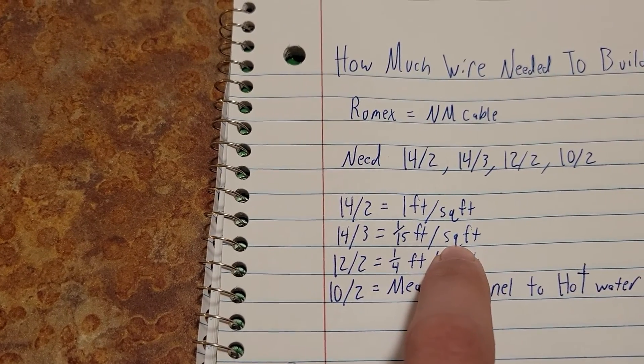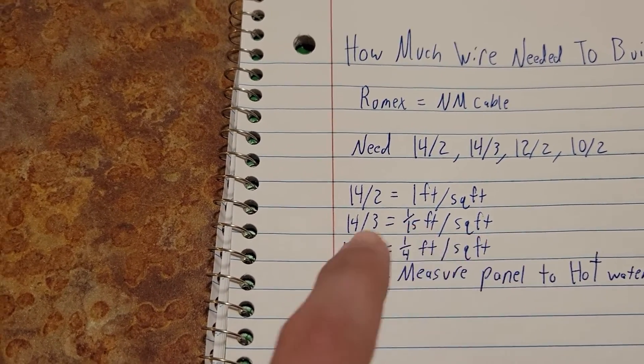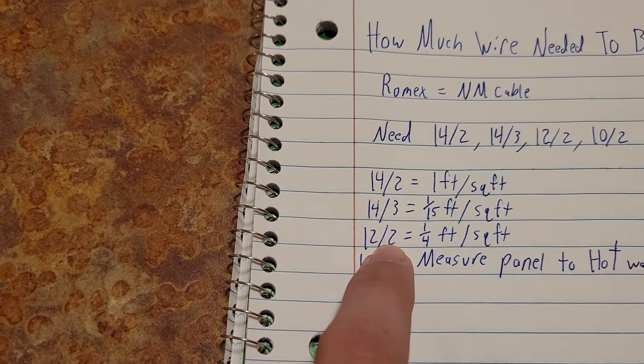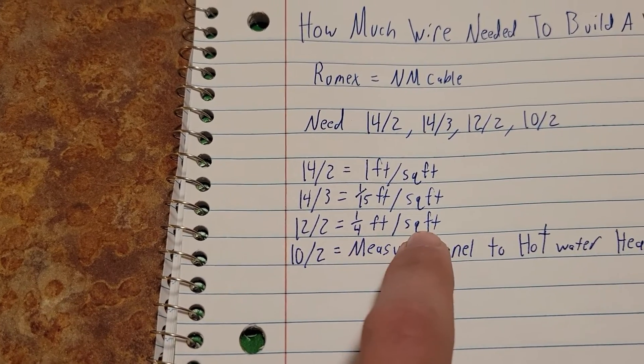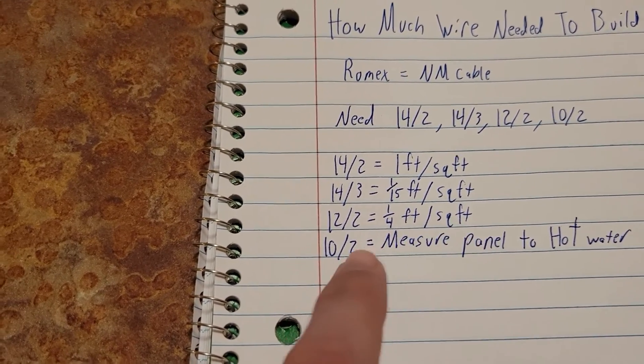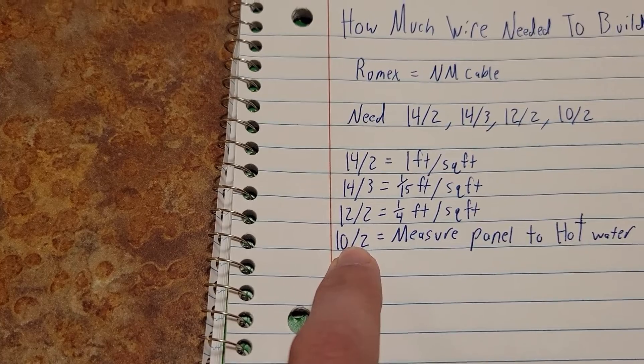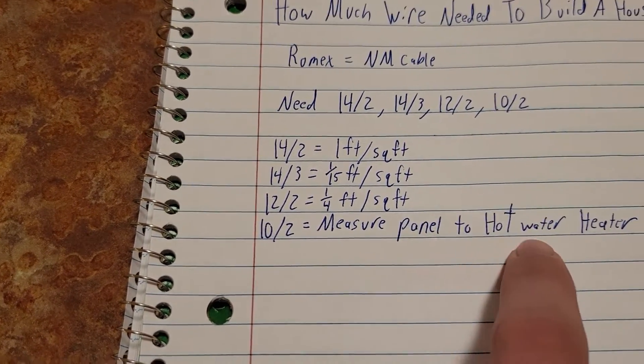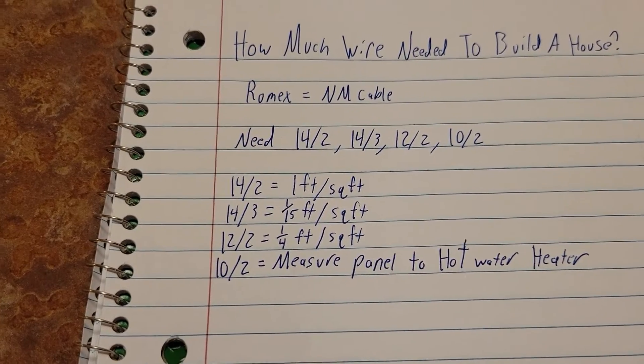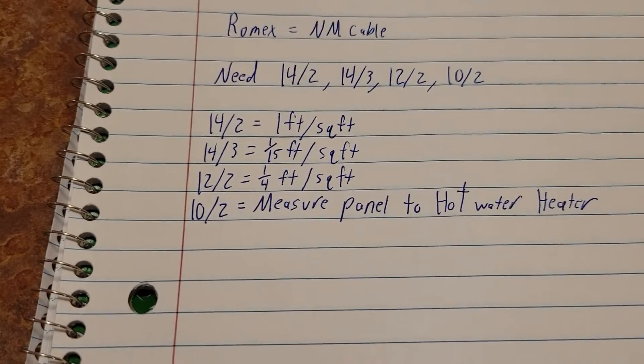To get the amount of 12/2 you're going to need, you're going to multiply 1/4 of a foot per square foot of the house. And to get the amount of 10/2 you're going to need, you're going to need to measure from your panel to your hot water heater location. That one I don't really have a good formula for because people put their hot water heaters in all different kinds of places, but the 10/2 is only needed for the hot water heater.